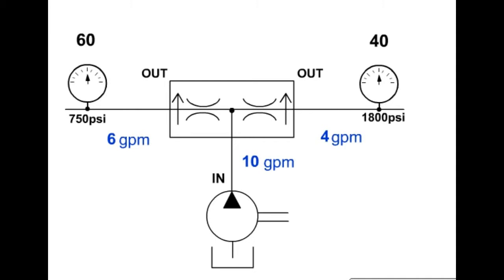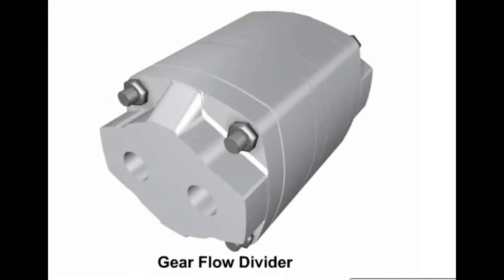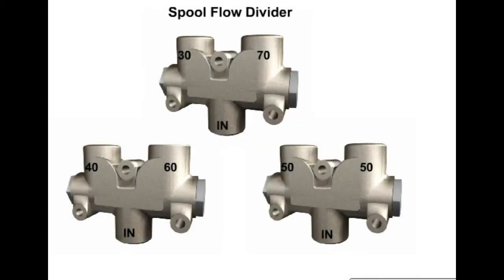The two types of proportional flow dividers are the spool and the gear or rotary. Spool-type proportional flow dividers divide the flow into two flow paths. The input flow is divided proportionally between the two output flow paths. Common flow divisions are 30-70, 40-60, and 50-50.